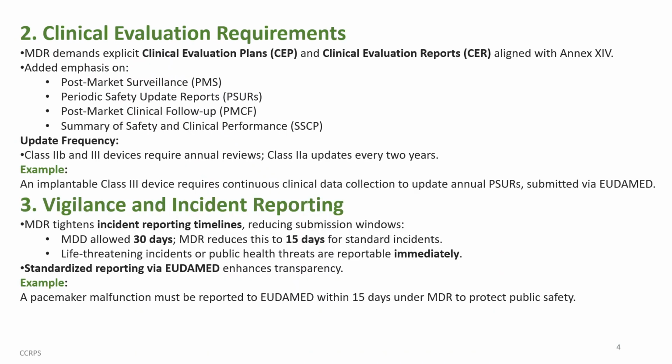Clinical evaluation requirements. MDR demands explicit CEPs, or clinical evaluation plans, and clinical evaluation reports aligned with Annex 14. Added emphasis on post-market surveillance, periodic safety update reports, post-market clinical follow-up, and summary of safety and clinical performance. Update frequency: Class 2B and 3 devices require annual reviews. Class 2A updates every 2 years. For instance, an implantable Class 3 device requires continuous clinical data collection to update annual PSURs submitted via EUDAMED.